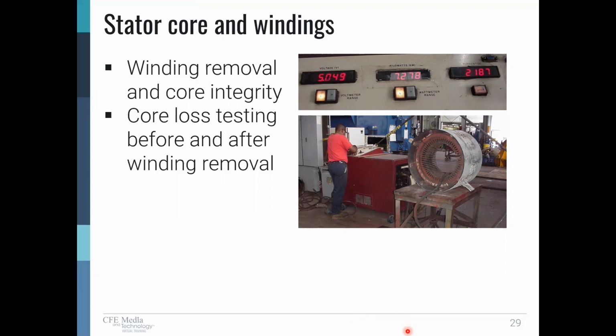So we have winding removal, core integrity. The picture we have here is a stator core with a very large, heavy wire going through it. And then this is the display from the meter. That's about 5.049 volts, and that's over 2,000 amps. So we've got a very low voltage, very high current.